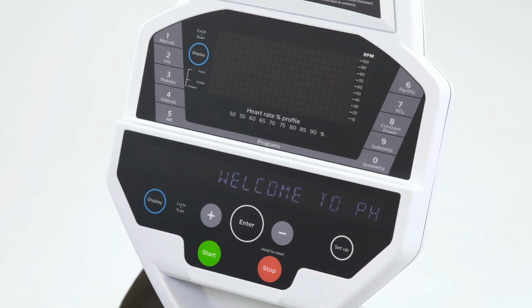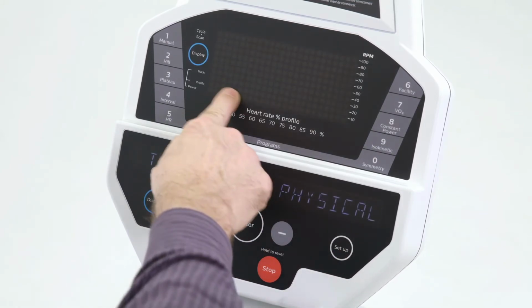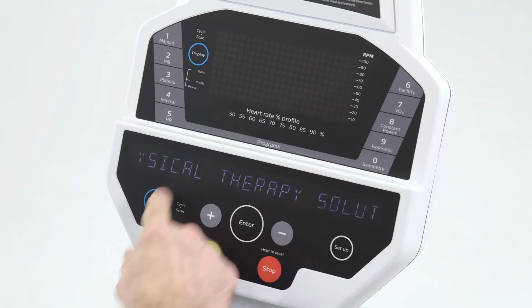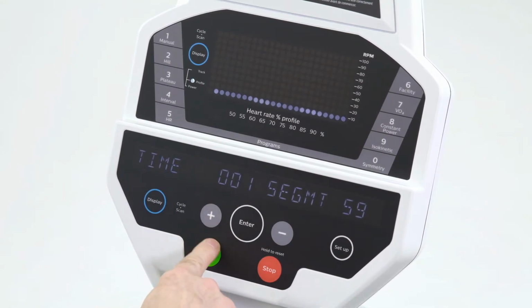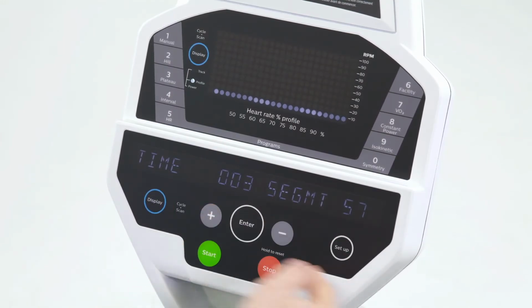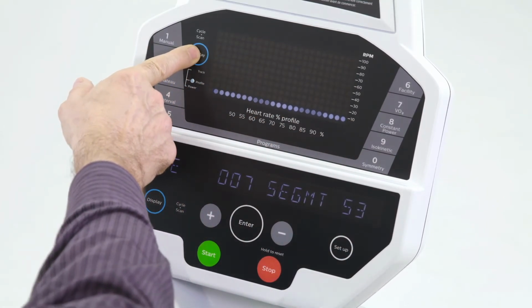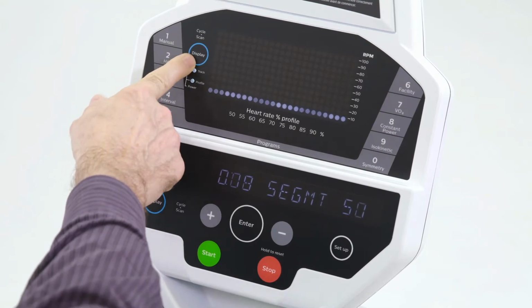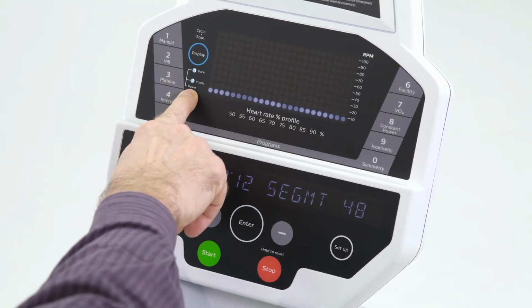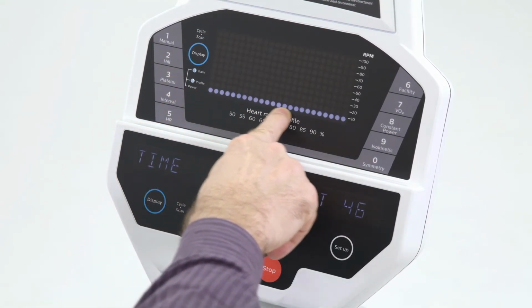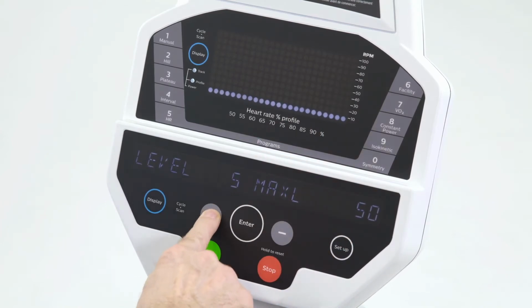In the setup, we were able to set up how many watts per row on our display, so I'm going to show how that works. So right now, the default was 10 watts per row. So right now I have 1 row of lights. If I come here and I press the display button, both of these light up, which indicates I am now in the power display. So this now indicates power.